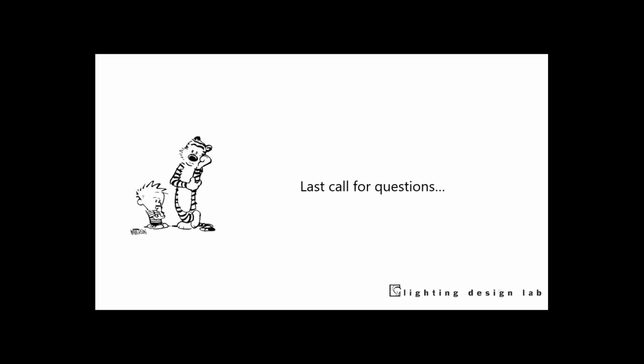So if they sent in some pictures of a light meter that showed high-end trim had dialed down light levels to 30 foot-candles, or some screenshots of how the configuration app has been set up, to me, that is so much more important than physically being there to count the fixtures in the ceiling, although I realize utilities aren't going to let go of that anytime soon.